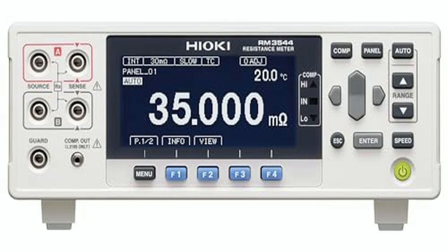The RM354401 positions itself as a precision resistance meter with an external I/O interface, promising basic accuracy across a range from virtually 0 up to 3.5 MΩ. That's a pretty wide span, meaning you could be measuring the tiny coil resistance in a vintage audio transformer one moment and the bulk resistance of a power cable the next. The key is how that translates into everyday use, and whether the trade-offs built into the design make sense for the kind of work you do.